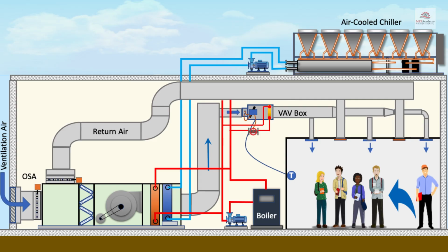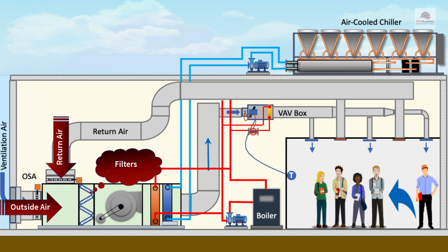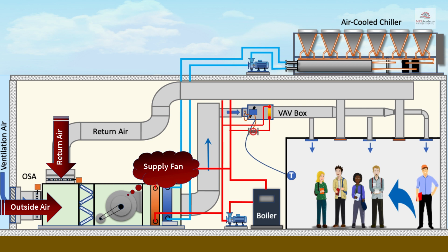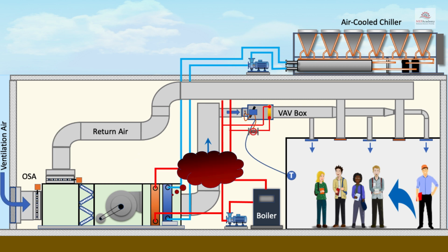Before we add a dedicated outside air unit, let's look at how ventilation air is normally brought into a commercial building using an air handling unit. This air handler mixes outside air with return air before entering the filter bank and then through the fan and a chilled water coil served by a roof-mounted air-cooled chiller.